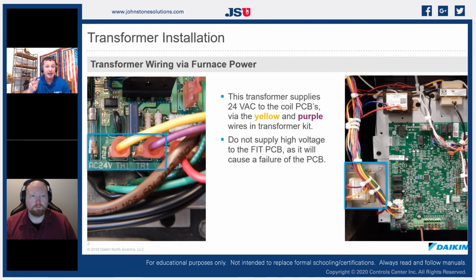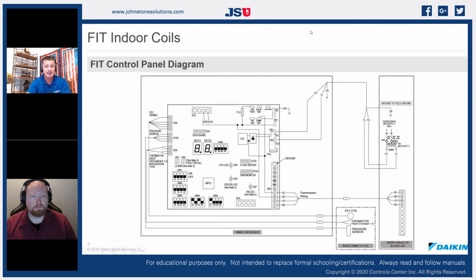So now if I have a zone control panel on this thing with a cased coil and a furnace, I've got 3 transformers and a power choke inside of that furnace cabinet, all of which have to be grounded, and our polarity has to be correct. So it's going to start with the correct installation of our transformers, just making sure that everything is going to the place that it needs to.